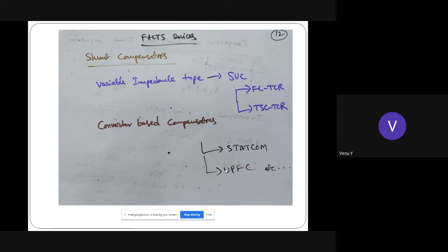Therefore, at light loaded conditions, you sense the Ferranti effect at the receiving end points. The receiving end voltage is higher than the sending end voltage. You need to provide inductive compensation at the load terminals, not capacitive compensation. If you place a fixed capacitor as a shunt compensator at the load terminal, it will further enhance the Ferranti effect problem and further increase the receiving end voltage.